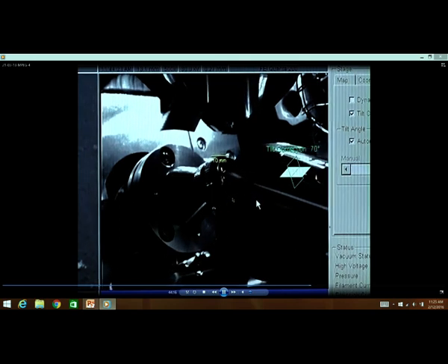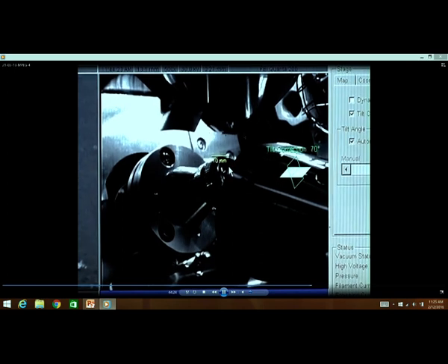So, this is a sample which is loaded in the specimen stage, and you can see that the specimen stage is tilted to about 70 degrees. Only then can you produce that very flat cone, and alpha can be very small. You can see that the EBSD camera just came in, and this is your pole piece.